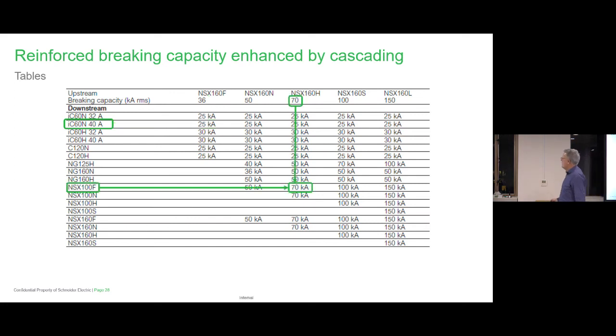So if that's the case, then that's good. And you can see here that was with a miniature circuit breaker, but here this could be in a subboard somewhere, but the fault level is still very close to those transformers. So this is in the main board. This could be in a subboard, could be in the main board as well. But we've put in an F, which is only rated at 36 kA, but its capability is up to 70. So we kept the cost down. The size of the board and so forth can all be affected. It's a brilliant thing to use, and we promote it.